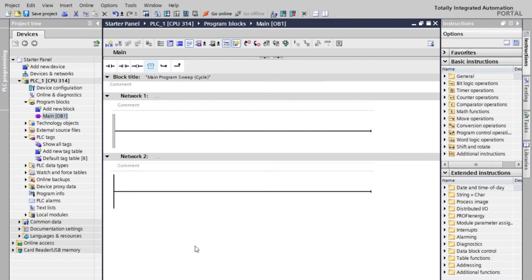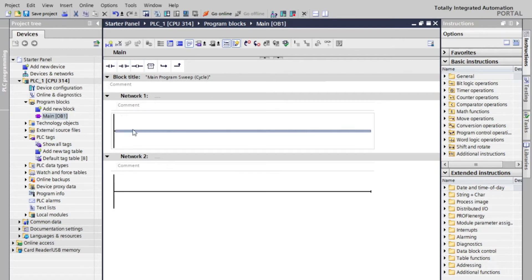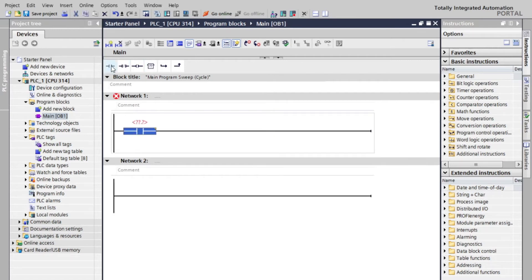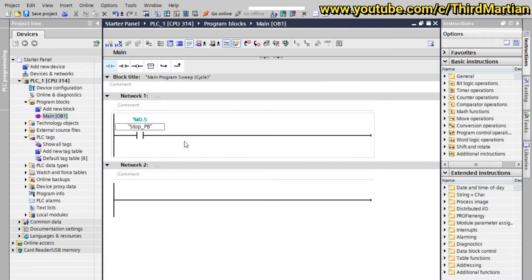In main OB1, for our first network, we will put an open contact for the stop button, followed by a closed contact for emergency stop activation.